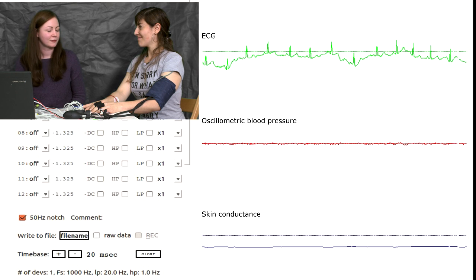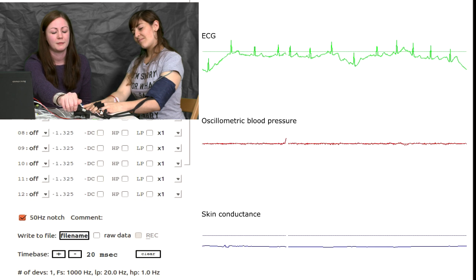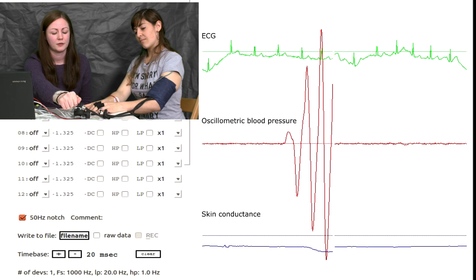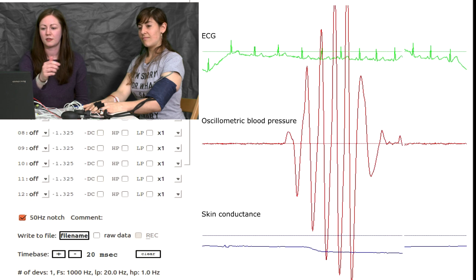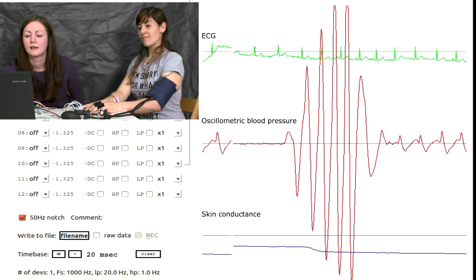And the next thing is to inflate the blood pressure cuff. So we're going to put that up to an intermediate level. So that's 70 for you. So you should see that appearing on the screen. That looks good.